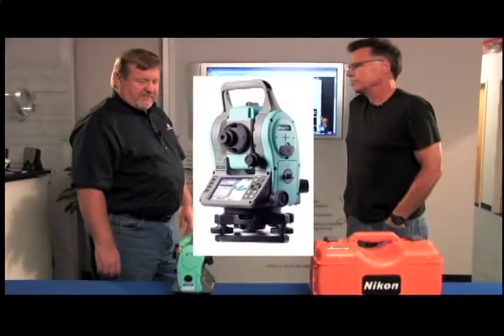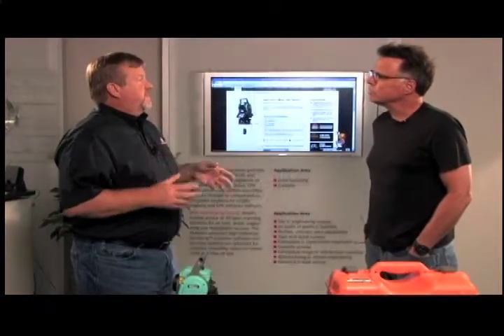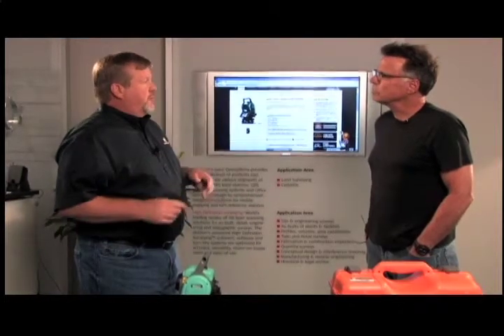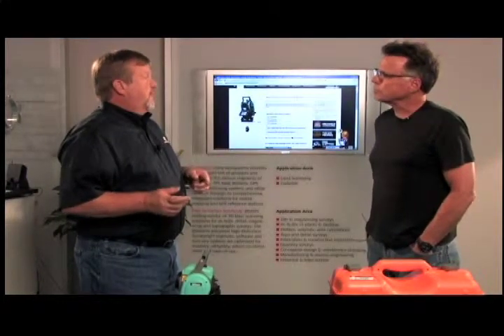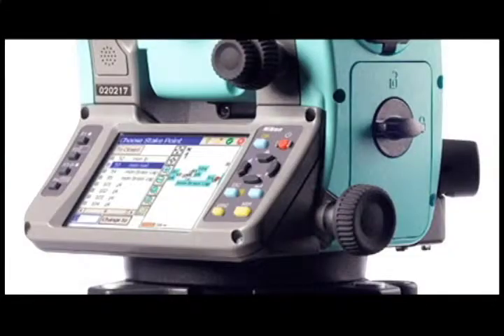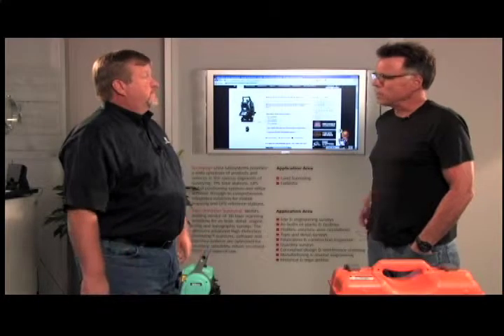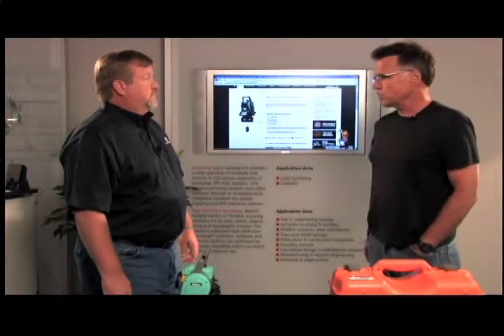The big difference of the Nivo C compared to the M is it has Spectra Precision Survey Pro on board. So you don't necessarily need a data collector to use the instrument in the field. All the computing is done on the instrument, and then you can take the data off just by plugging in the USB stick and taking it back to the office to upload the information. Meanwhile, this is still working out in the field.